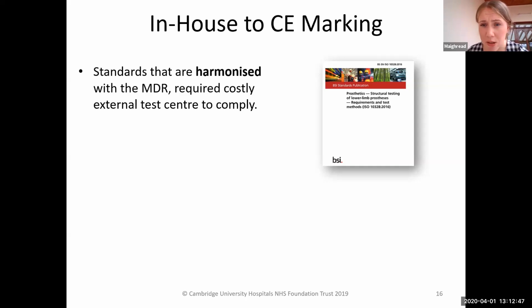And in this instance, there are some harmonized standards for lower limb prosthetics. So I've just showed an image of one here. Therefore, if we wish to CE mark our device, we would then also have to comply with these harmonized standards. And to do that, there are test centers available which will test your product under very controlled conditions, but this does come with a cost.